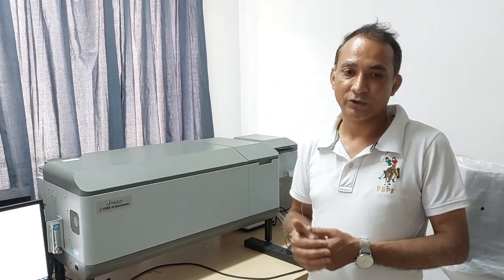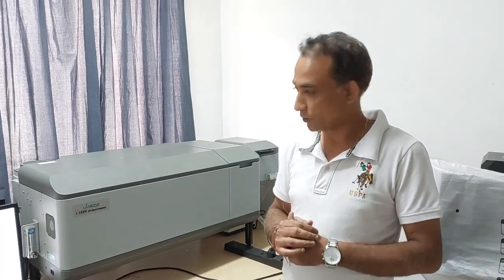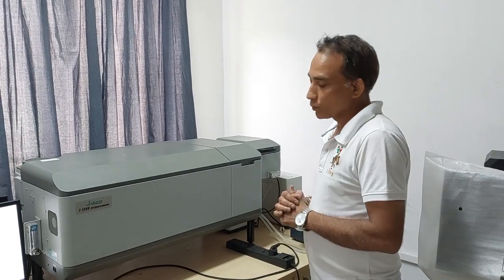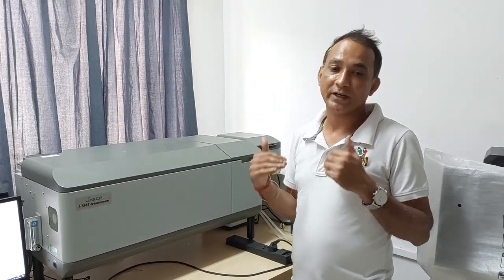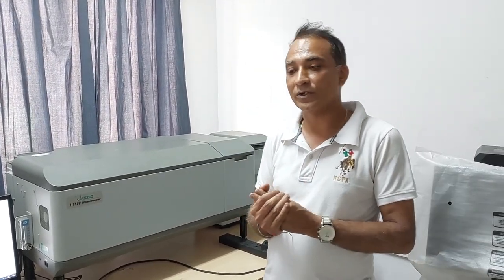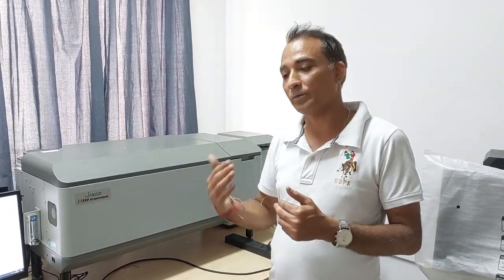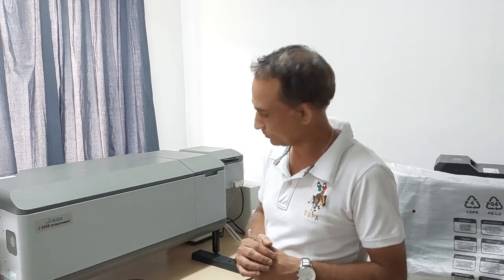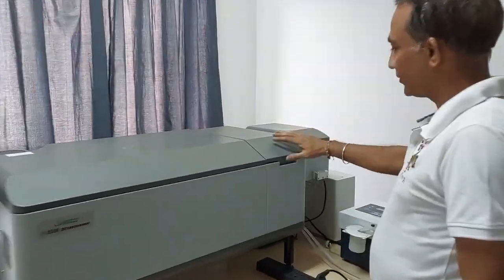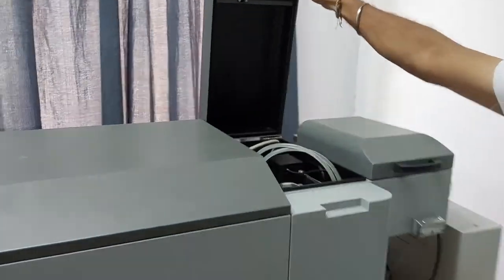You set up what range of wavelength you are going to record your spectrum. You select the slit widths, the scan speed, and the digital integration time for your data. Once you are done with that, you also have to select the number of accumulations. CD spectra generally have a low signal to noise ratio. So to improve the signal to noise ratio, you record multiple spectra, and the average of those spectra is presented as the final data. So this is the chamber where you place your cuvette.